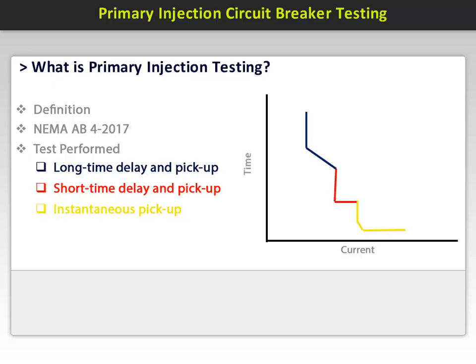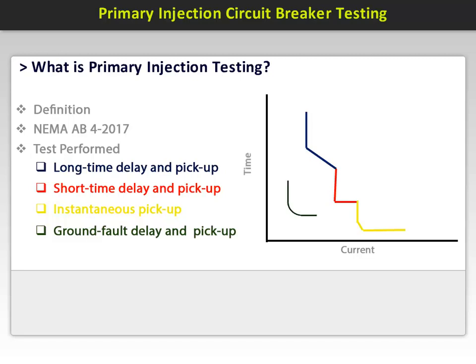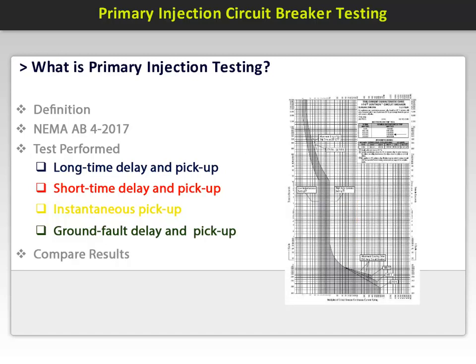The last test is ground fault delay and pickup, shown as the green line on the curve. These are usually low current. Current is injected and the trip time is recorded. The results of all these tests are compared with the manufacturer's published trip curves to determine if the breaker is operating within the specified limits.